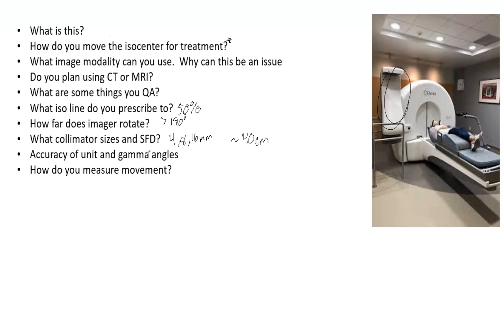What is the accuracy of this unit and the gamma angles associated? The big driving force to have a Gamma Knife is that it is extremely accurate and fairly simple. With those cobalt sources, we are able to get within 0.3 millimeter accuracy. In comparison, a linear accelerator is approximately 0.5 millimeter, so the Gamma Knife is more accurate. We have gamma angles at 70, 90, and 110 degrees — these are the angles that the head can be placed in to give you better access to the tumor as you are radiating it.